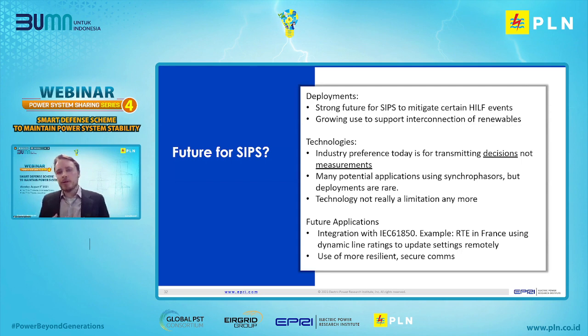Previously, most systems were based on transmitting decisions, so trip commands or breaker status, whereas we're seeing more systems being deployed with synchrophasors, where they communicate measurements to a central location to determine the decision. This is becoming increasing in usage. We're seeing a lot more use of IEC 61850 for communications. For example, RTE in France are using dynamic line ratings. They're looking at using dynamic line ratings to dynamically change their relay loadability and relay settings in real time and to make better use of these technologies. And finally, then my conclusions on the next slide.